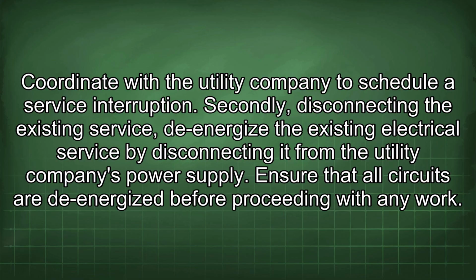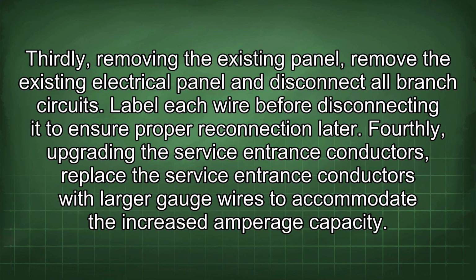Secondly, disconnecting the existing service de-energize the existing electrical service by disconnecting it from the utility company's power supply. Ensure that all circuits are de-energized before proceeding with any work. Thirdly, removing the existing panel. Remove the existing electrical panel and disconnect all branch circuits. Label each wire before disconnecting it to ensure proper reconnection later.